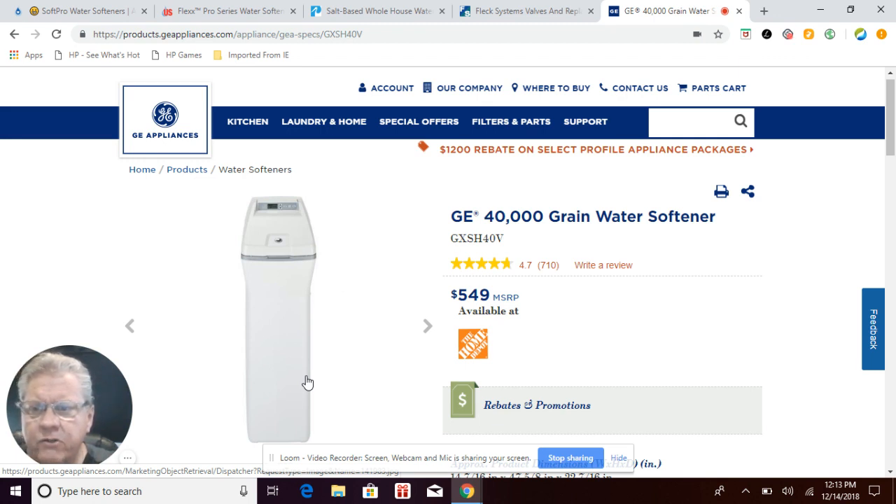The mineral tank inside, with the control valve attached, sits inside the salt tank. The disadvantage is that you're exposing your electronic components to salt air by having everything in one tank, which is bad for the electronics over time.